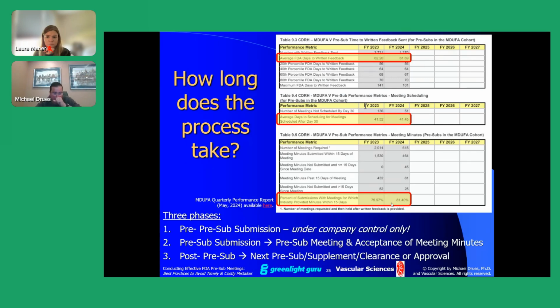And then finally, the post pre-sub phase, where you might be working on your next pre-sub, you might be working on a pre-sub supplement, you might be working on your clearance or approval. And another thing that you should understand about pre-subs is the opportunity to do a pre-sub supplement. A pre-sub supplement is nothing more than a little kind of a focused pre-sub where you can go back to the FDA with additional information. The only caveat to submitting a pre-sub supplement is that the topic has to be addressed in the original pre-sub.